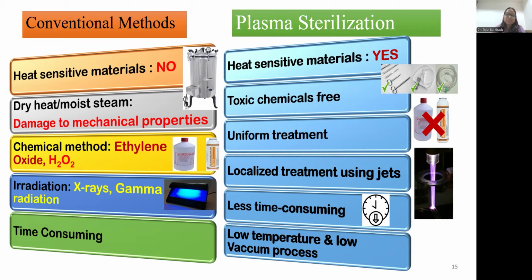It can be sterilized at the localized place, and it also takes very little time. Maximum we can have 5 to 10 minutes of sterilization time for the complete cycle. Then also we use low temperature and low vacuum processes. So these are some benefits of this alternative plasma sterilization method, which we can apply and use in our healthcare settings or hospitals.